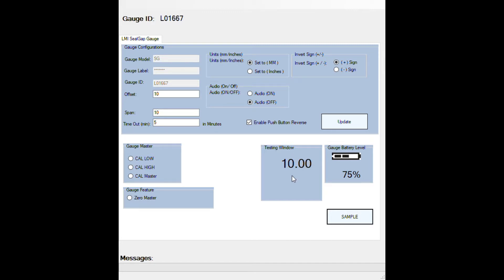To simply zero your gauge, you can come in here and click on zero master and then click sample. This will automatically zero your gauge without having to go through the high and low steps.